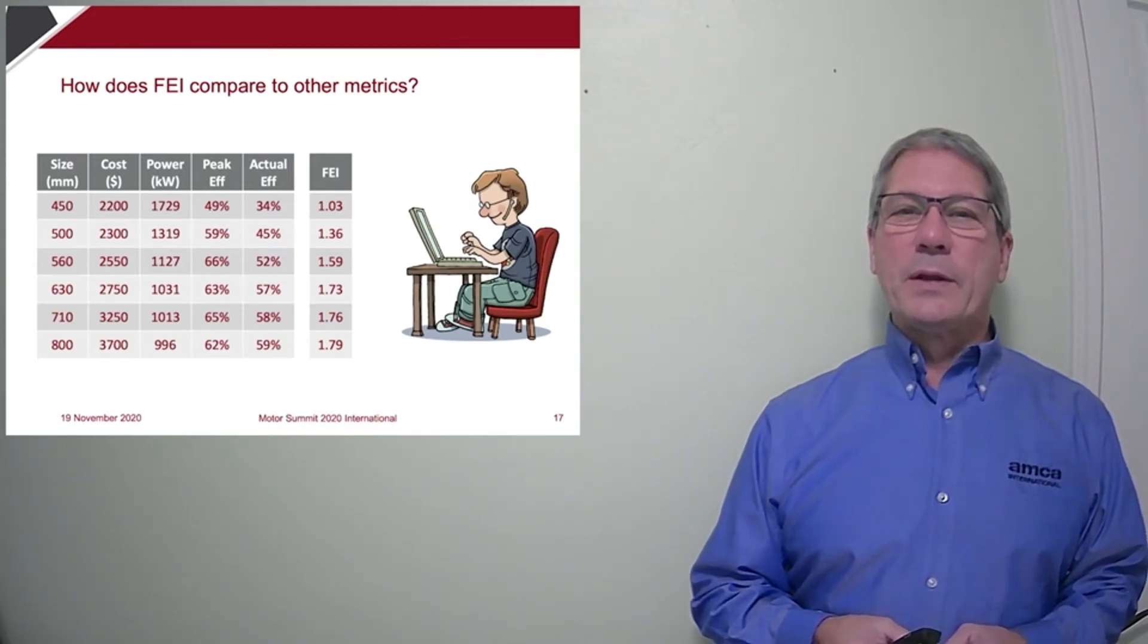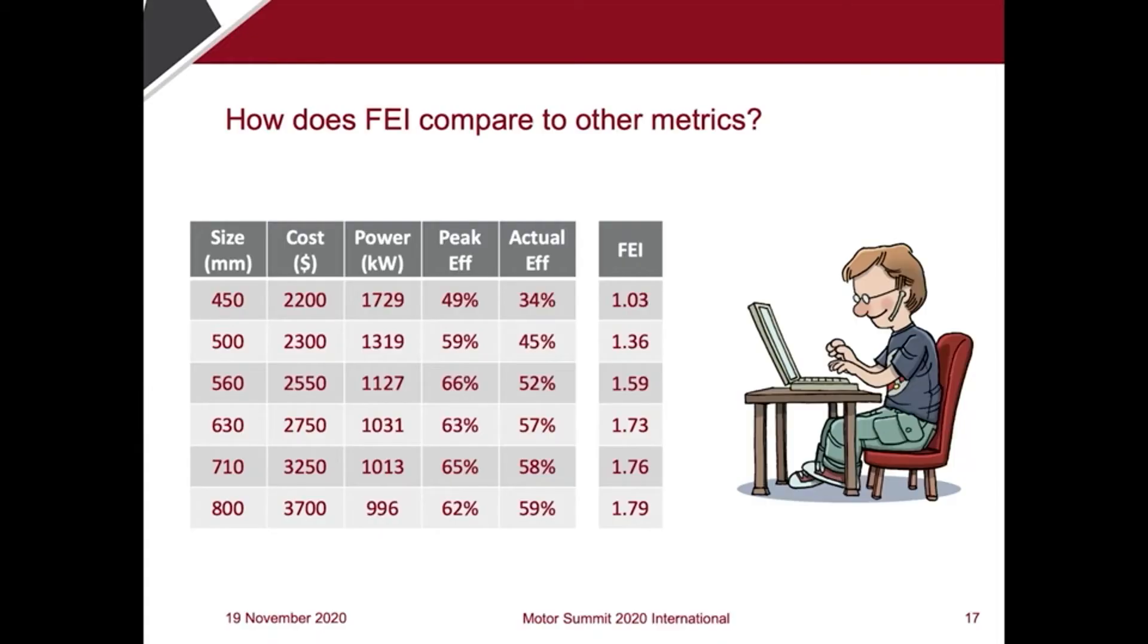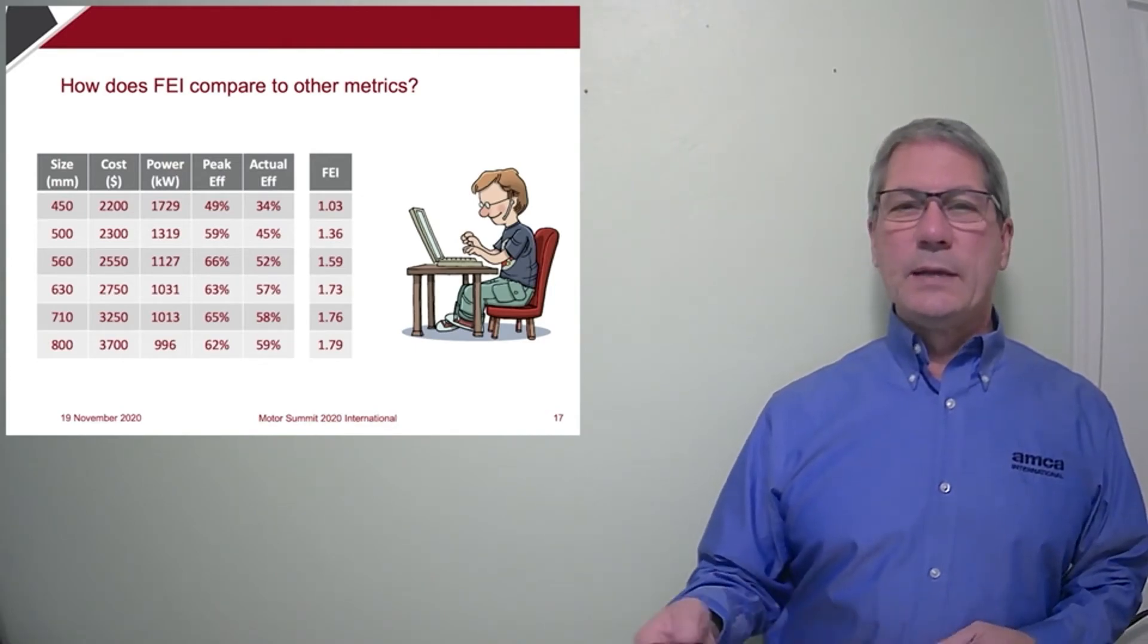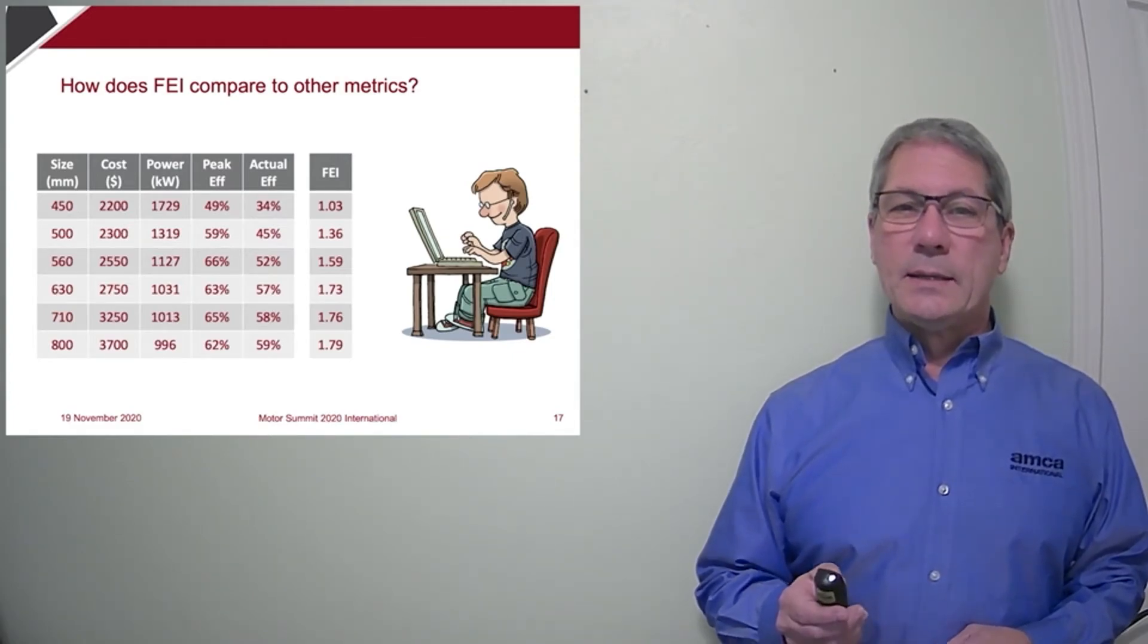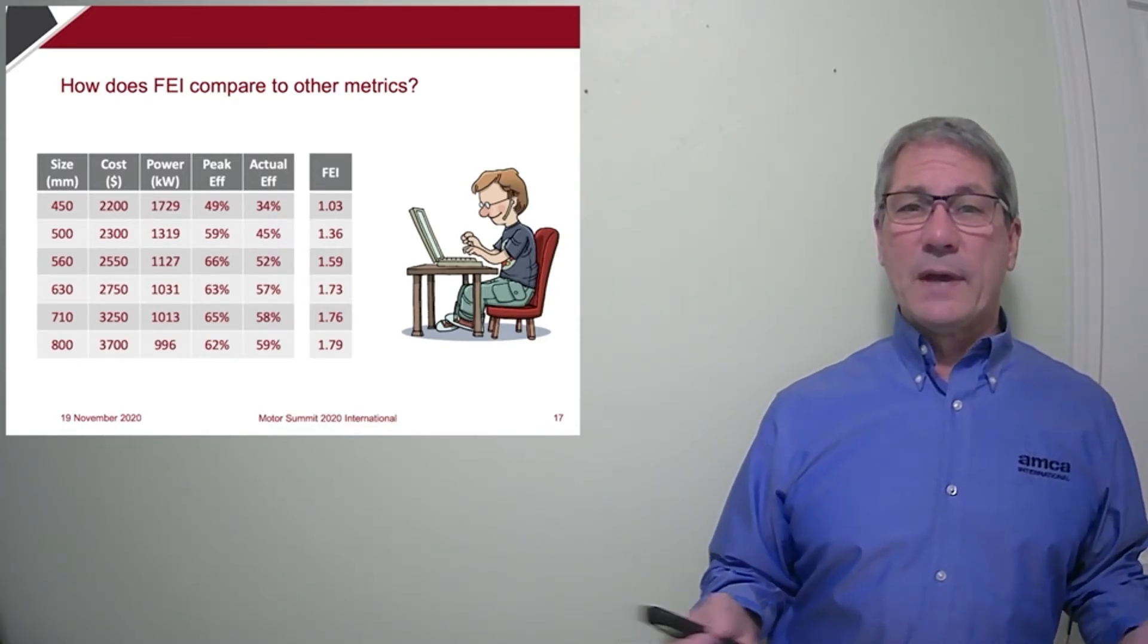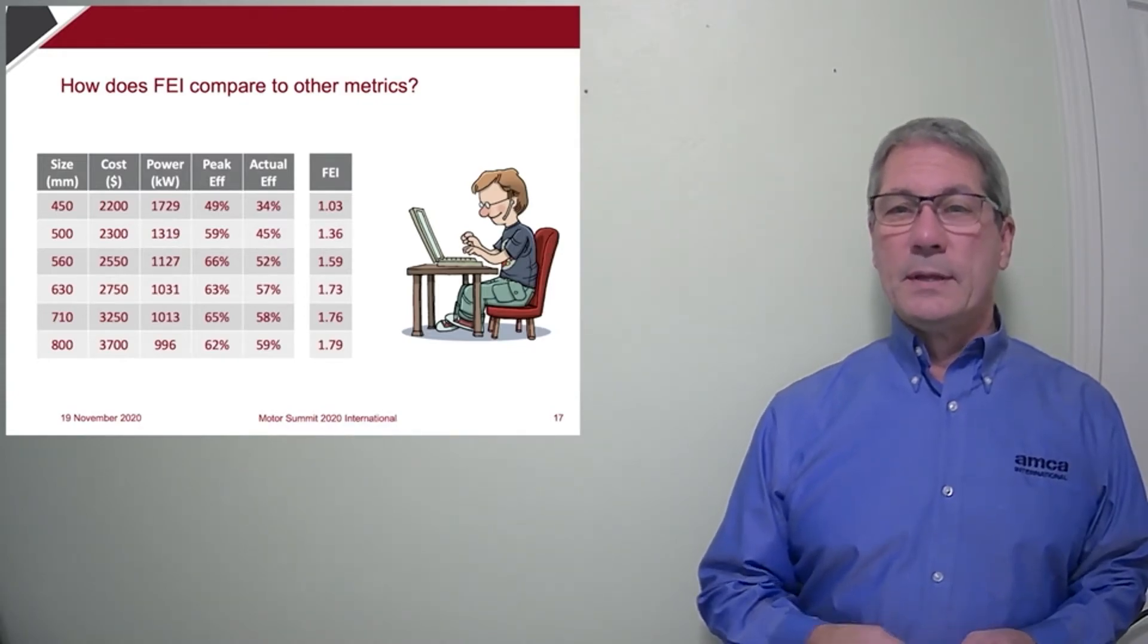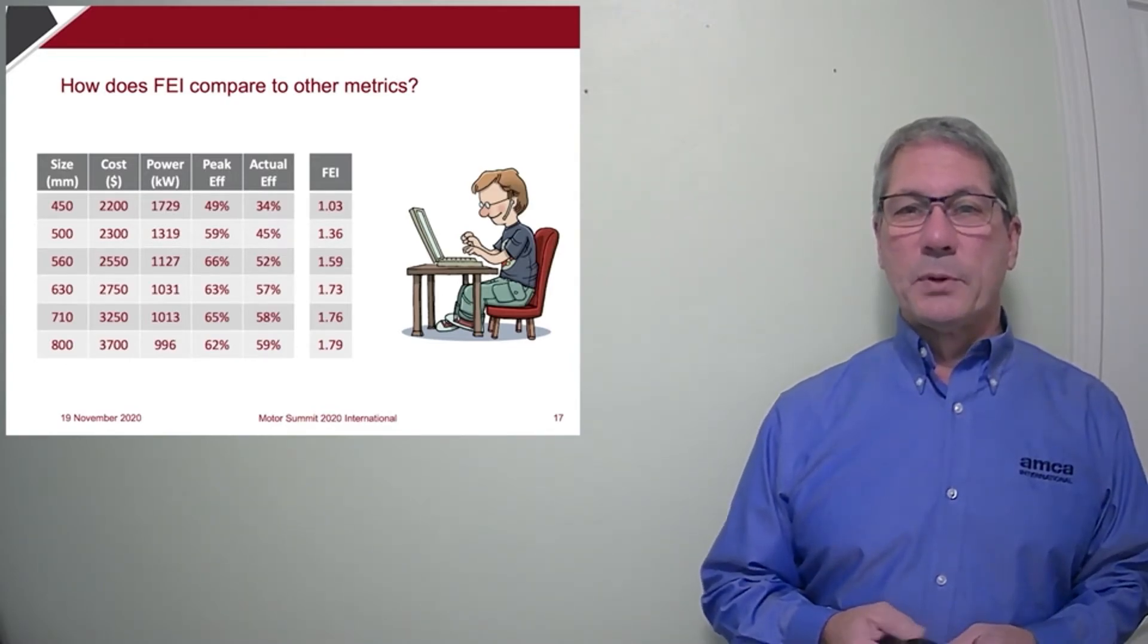So how does FEI compare to other energy efficiency metrics? And remember, you get what you measure. Well, any peak efficiency metric, whether it's FEG or FMEG, will have about the same, if not exactly the same value for each of these fan sizes, since they're the same model. And this happens to be a very efficient model. So any of these sizes will pass based on any peak efficiency metric. But FEI is focused on the decision maker. In this example of simply picking the fan size, there's about a 75% difference in power consumed. And the FEI value varies by 75%. A perfect correlation.